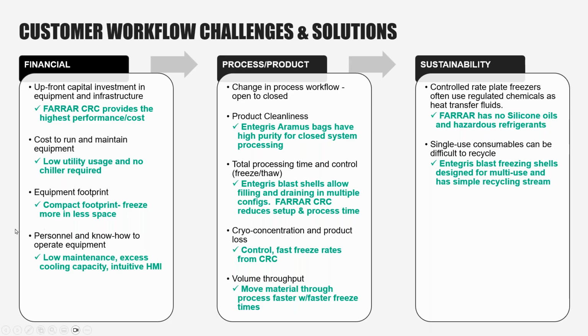From the process and product challenges, we began with the vessel like we talked about, and we talked about the challenges with bottles. The Aramus bag materials are made with high purity materials and equipped with 3 lines for closed system processing, minimizing contamination. Both the FARRAR Model 4000 and the Entegris blast shells significantly simplify the processing by allowing draining and filling in multiple orientations and configurations, and the bag's airflow promotion design increases the freezing speed when paired with a 4-stair blast freezer like FARRAR. These faster freezing times also reduce cryo concentrations, where the water in the solution freezes first, allowing the non-water drug substance material to concentrate and possibly become damaged, as well as increase processing speed through the freezing step.